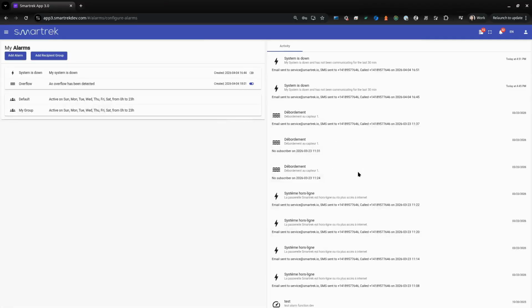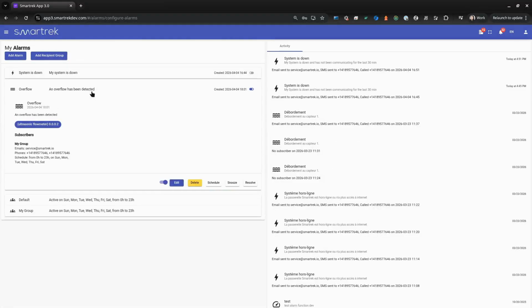Enter the text you'd like to receive, then configure the following options. Set a repeat interval of 5 minutes, ignore 2 or 3 alarms to filter out sudden fluctuations in the water level reading, and set an automatic rearm time of 5 minutes. Your alarm is now created and will send you an alert if your sensor has measured a level above the threshold for more than 15 to 20 minutes.